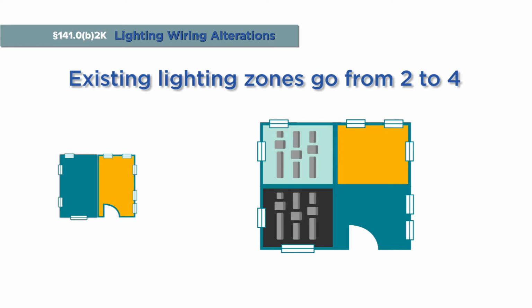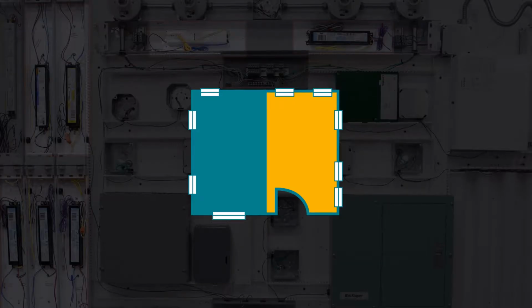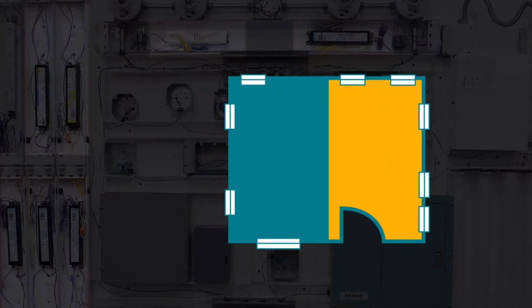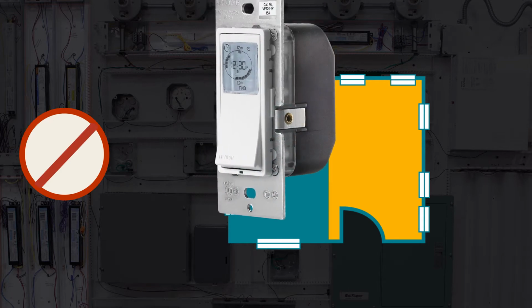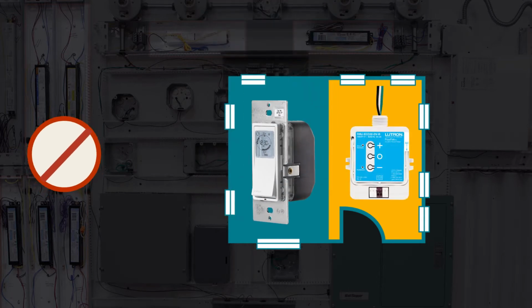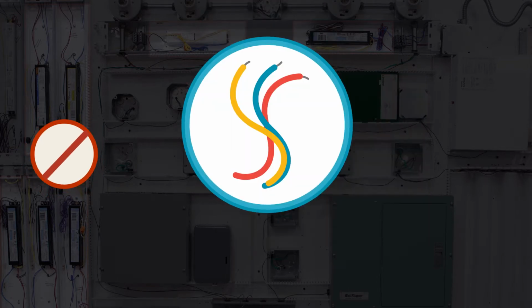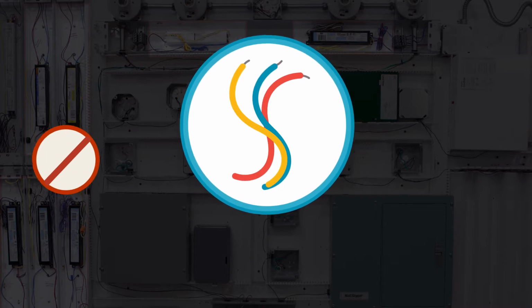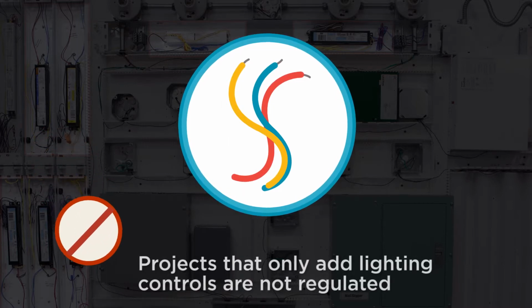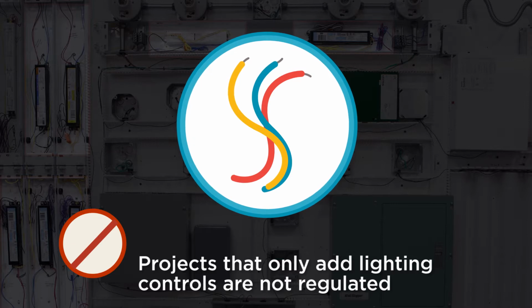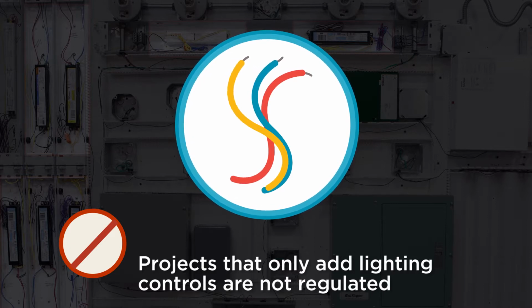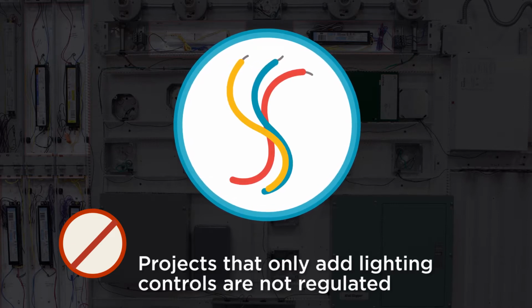This project is now considered a lighting wiring alteration under the Energy Standards and is regulated under Section 141.0B2K. A project that would not be covered under this category, for example, would involve only adding new occupancy sensors in existing lighting zones. Lighting wiring alterations strictly limited to the addition of new lighting controls are exempt from the lighting wiring alteration requirements, even though they do involve wiring changes.